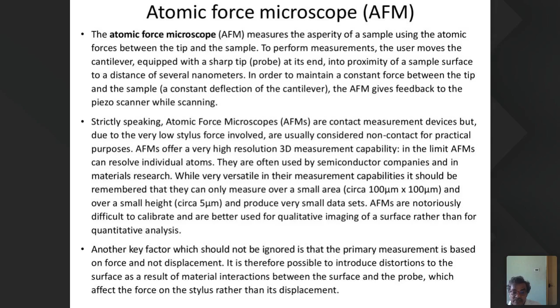AFM offers very high resolution 3D measurement capability. The limit of AFM can resolve individual atoms. AFM is notoriously difficult to calibrate. That is a limitation, but it is better used for qualitative imaging of the surface rather than for quantitative analysis. Another key factor which should not be ignored in the AFM is that the primary measurement is based on the force and not the displacement. It is therefore possible to introduce distortion to the surface as a result of material interaction between the surface and the probe.